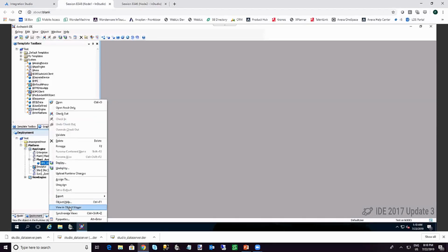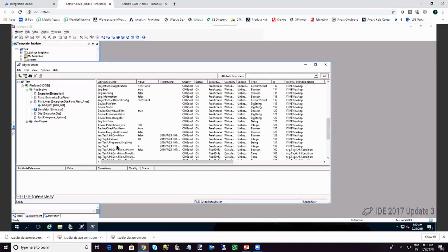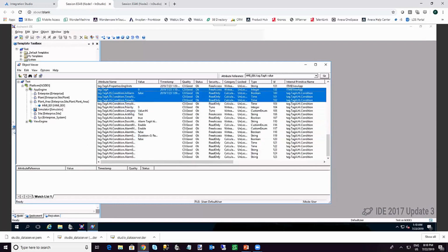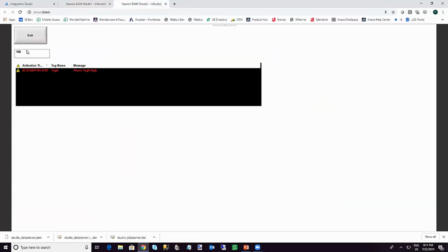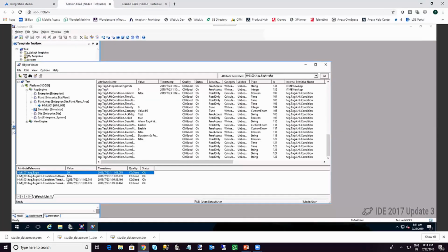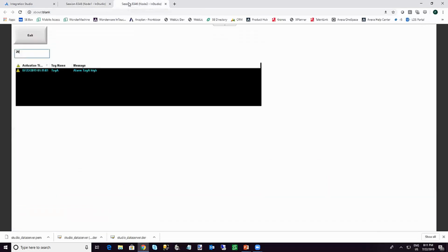And if I go to InTouch Edge HMI and go to Object Viewer, I have the tag A. Now it's connected to the runtime using the authentication settings that I configured on the object. And the communication still works. So if I drag here tag A and change the value to 100, it changed the value to 100 here. If I change the value to 20 here, it changes the value back to 20 there. So it's still communicating the same way.